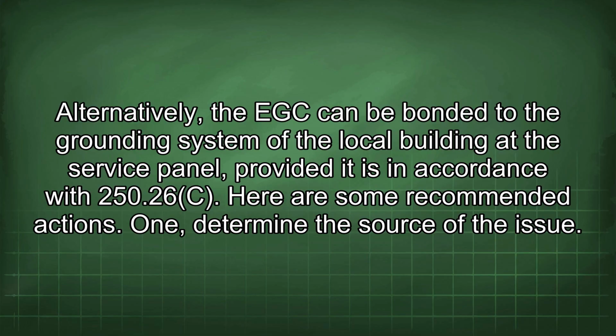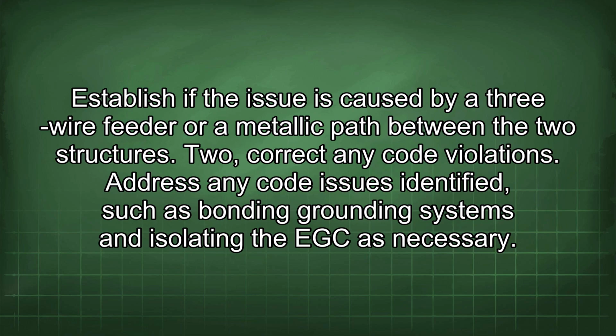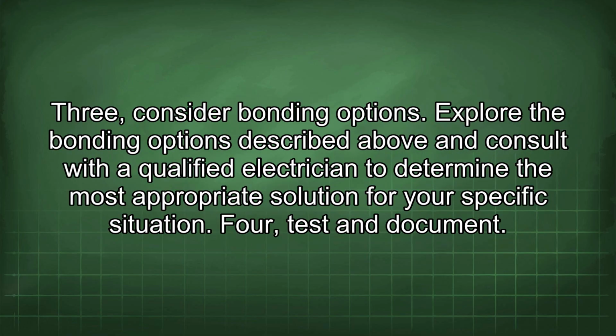Here are some recommended actions. 1. Determine the source of the issue. Establish if the issue is caused by a 3-wire feeder or a metallic path between the two structures. 2. Correct any code violations. Address any code issues identified, such as bonding grounding systems and isolating the EGC as necessary. 3. Consider bonding options. Explore the bonding options described above and consult with a qualified electrician to determine the most appropriate solution for your specific situation.